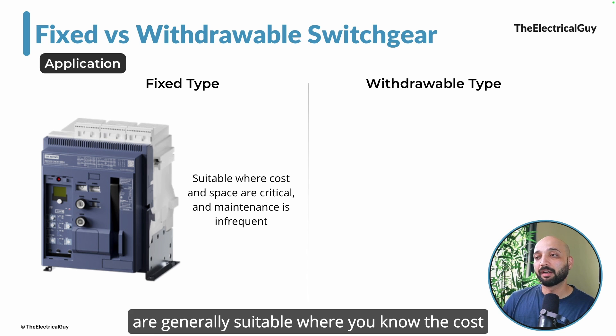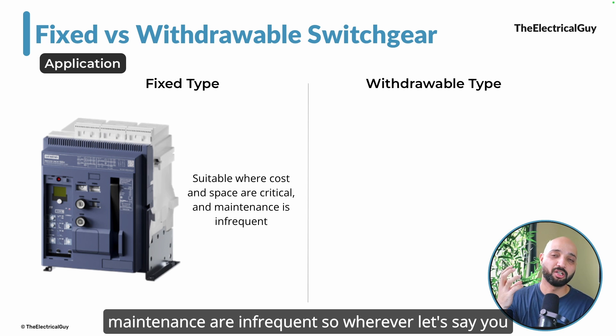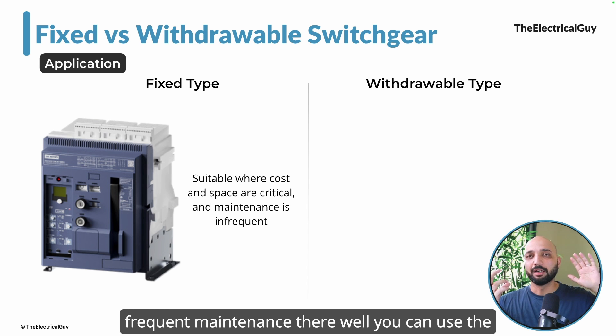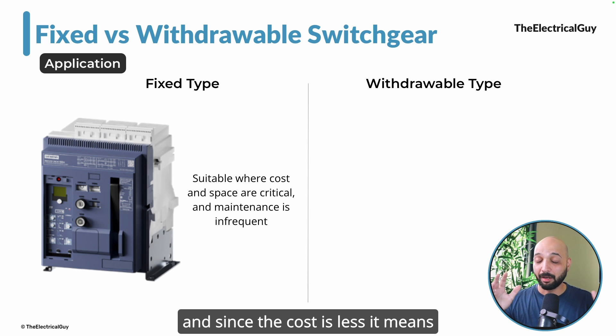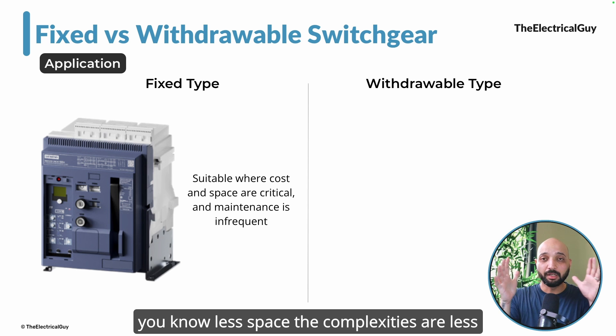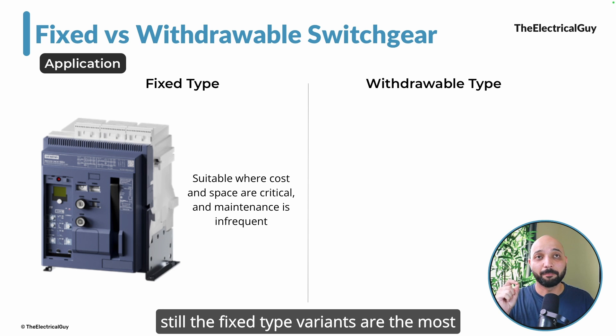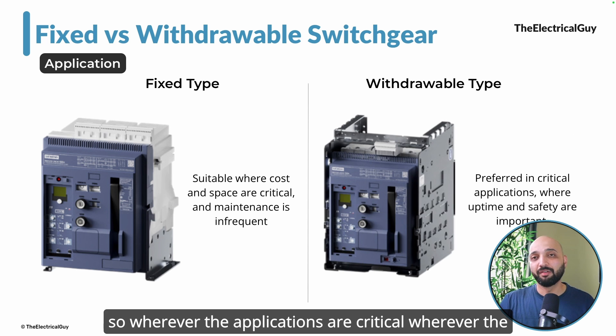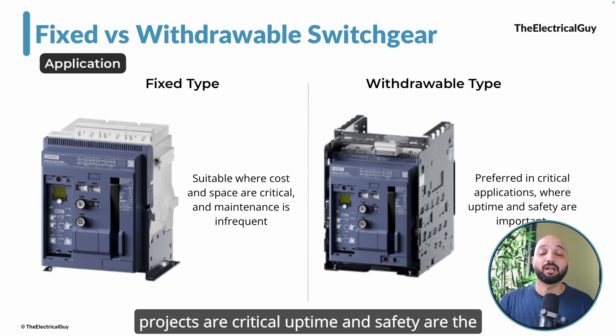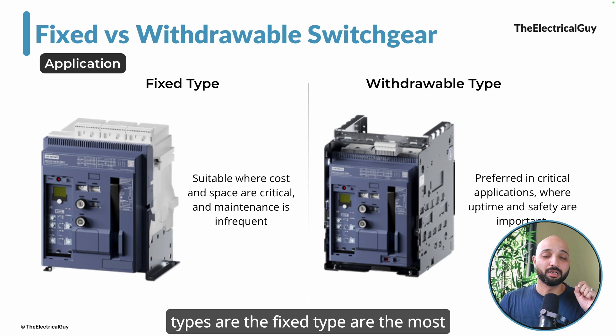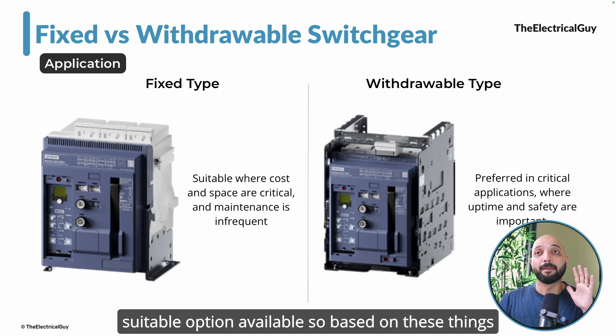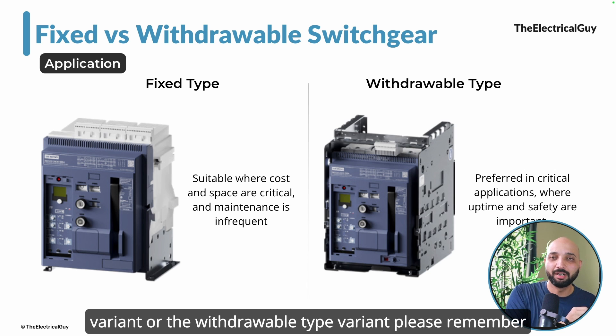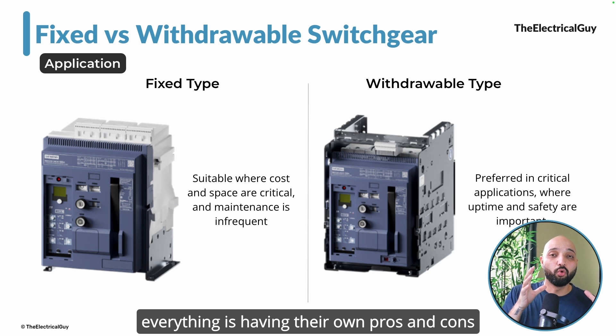Regarding application: fixed type variants are suitable where cost and space are critical and maintenance is infrequent — for example, simple unmanned transformer substations. Despite higher cost and complexity of withdrawable types, fixed type variants are still the most sold. Withdrawable types are the best choice where applications are critical and uptime and safety are the most important parameters, such as critical industrial facilities and hospitals.